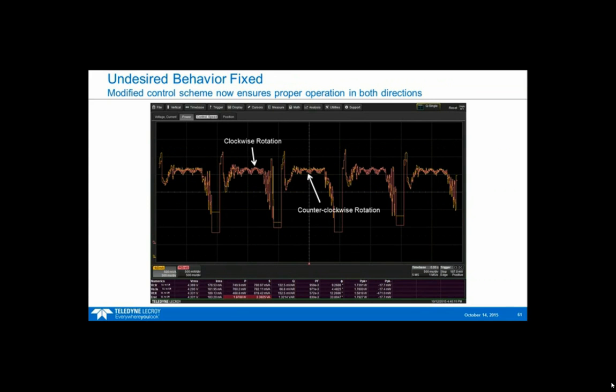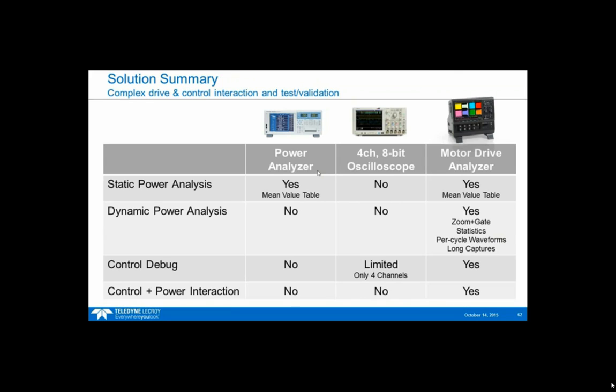Based on that information, the customer was able to find the problem in their control scheme and modified it. Once they did that, they took the acquisition again and the problem was fixed. Now they have much less oscillation than before, and the clockwise and counterclockwise rotations match in a much better way.